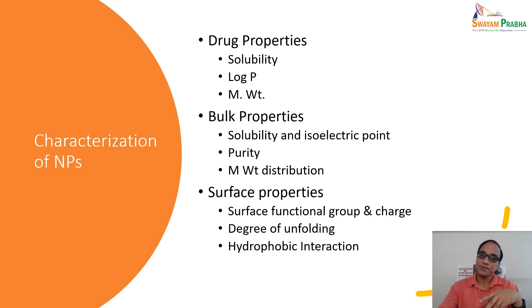Now, the first and foremost thing is surface morphology and size. This is the holistic view which I am giving to you. Dynamic light scattering, DLS, gives the hydrodynamic radius of the particle. It is a very expensive instrument, but very fast and very reliable. We can have the nanoparticle size distribution and zeta potential analysis with the help of DLS. Basically, laser light scattering is determined in this instrument, number one. And number two, photon correlation spectroscopy, in which velocity distribution is obtained by measuring the dynamic fluctuation of scattered light, and we can have the average size, polydispersity index analysis, etc. In DLS we can also have the polydispersity index.